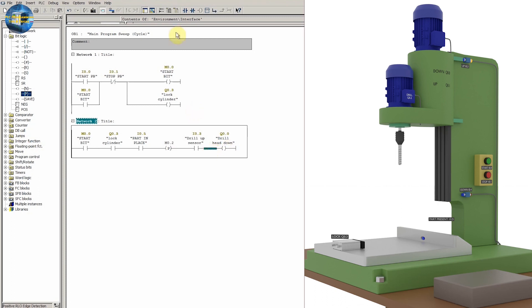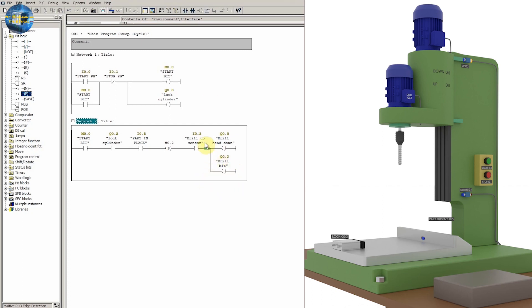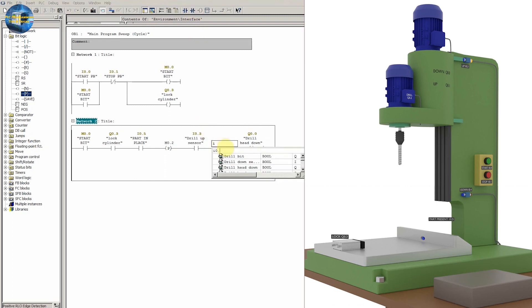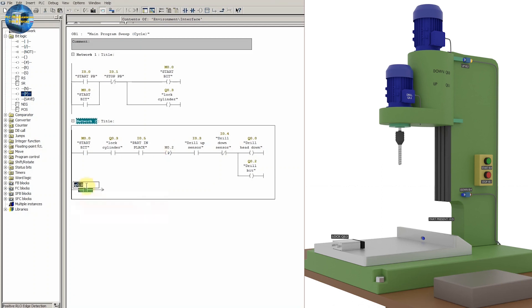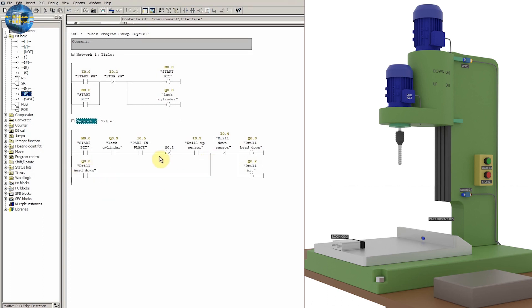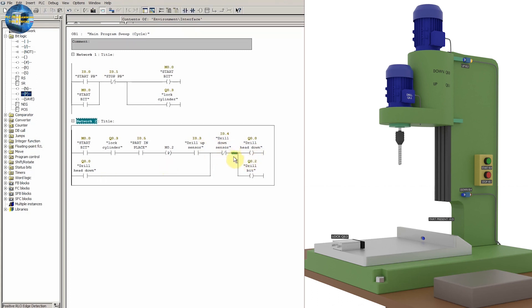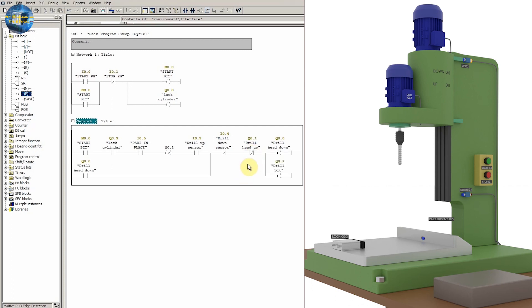Along with the drill head moving down, we also turn on the drill bit motor Q0.2. We can turn off these two outputs by putting the normally closed contact of the down sensor I0.4 in series, so that Q0.0 and Q0.2 turn off once the drill head reaches the down limit sensor I0.4. We also insert a normally closed contact of drill head up output Q0.1 as an interlock, allowing Q0.0 to turn on only when Q0.1 is off.